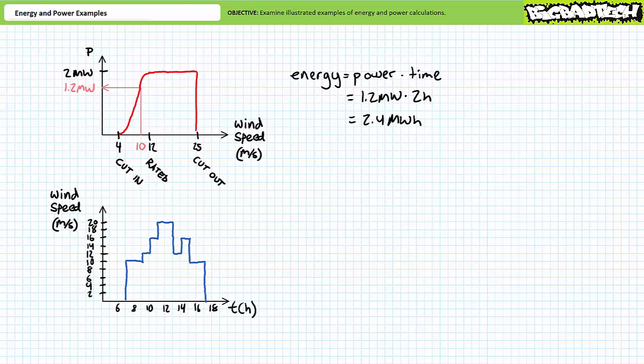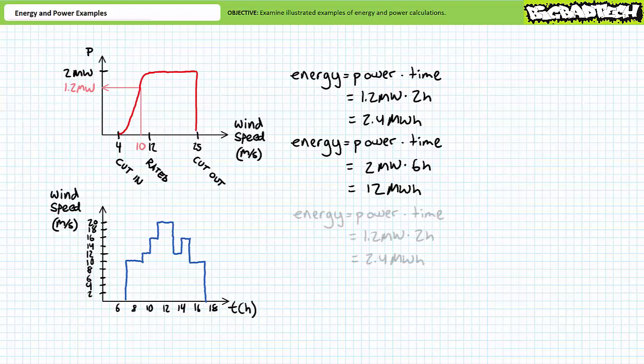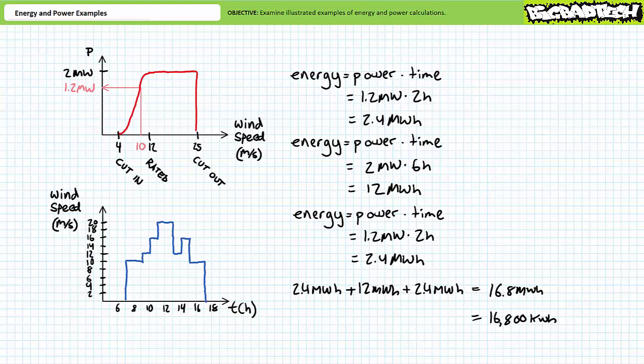For the first two-hour period at 10 meters per second wind, the turbine produces 1.2 megawatts times two hours, or 2.4 megawatt hours. For the middle six-hour period at 12 meters per second or greater, the turbine produces two megawatts times six hours, or 12 megawatt hours. For the last two-hour period at 10 meters per second, the turbine produces 1.2 megawatts times two hours, or 2.4 megawatt hours. In summation, the turbine produces 2.4 + 12 + 2.4 megawatt hours, or 16.8 megawatt hours of energy, which we could also express as 16,800 kilowatt hours.